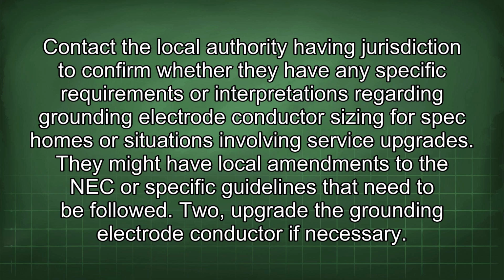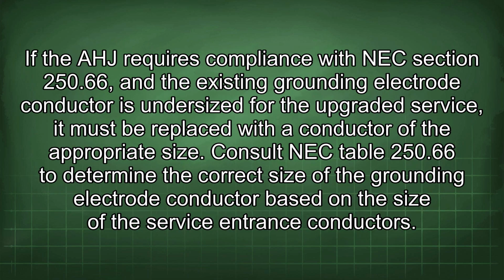2. Upgrade the grounding electrode conductor if necessary. If the AHJ requires compliance with NEC section 250.66, and the existing grounding electrode conductor is undersized for the upgraded service, it must be replaced with a conductor of the appropriate size. Consult NEC table 250.66 to determine the correct size of the grounding electrode conductor based on the size of the service entrance conductors.